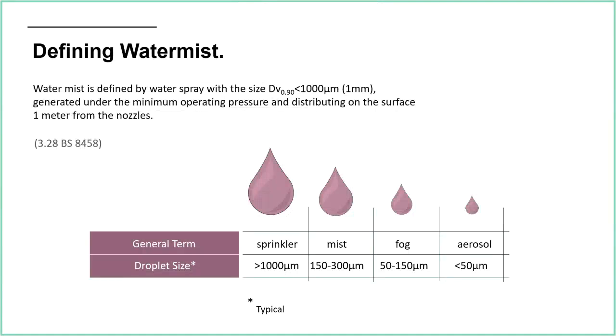1,000 micrometers is 1 millimeter, so they're saying 90% of the droplets will be smaller than 1 millimeter when generated under the minimum operating pressure and distributed onto a surface 1 meter from the nozzles. I've not actually seen this done in real life, but I imagine they have some sort of screen - they set off the nozzle at 1 meter distance, run it at the minimum operating pressure, and use some sort of camera to analyse the size of the droplets created. If 90% of them are less than 1 millimeter, it would officially be water mist.